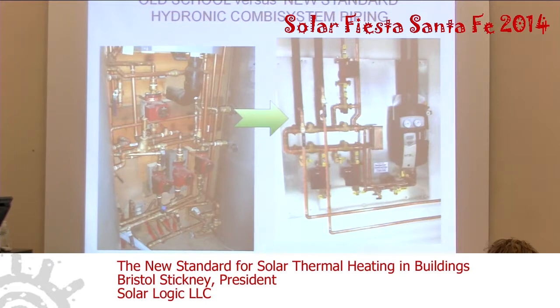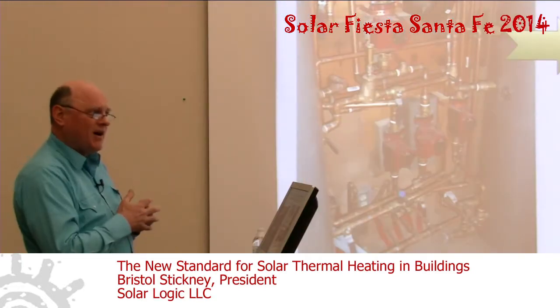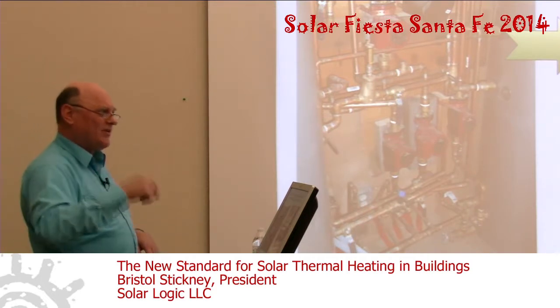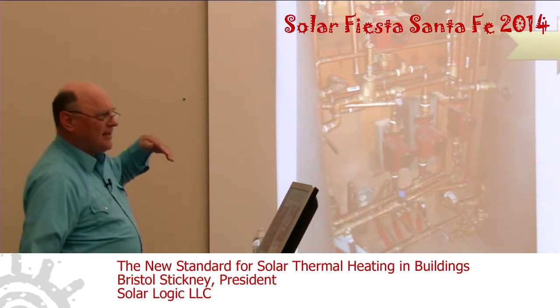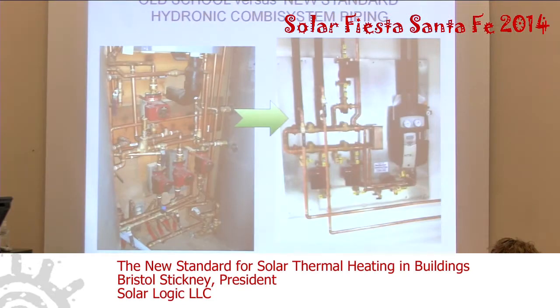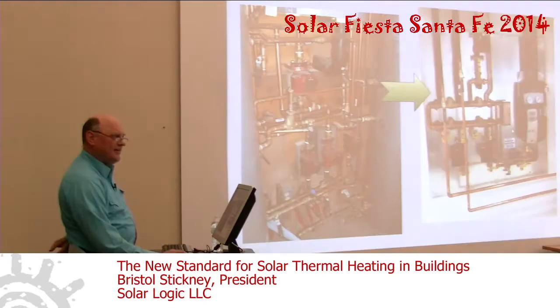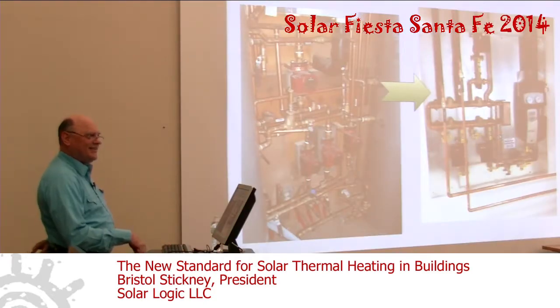It's a primary loop. It's a loop of plumbing with two T's taking heat away and pulling heat in, and a solar heat exchanger somewhere in the loop that delivers solar heat into the loop. So literally, these two plumbing photographs do the same thing. They both have 4 pumps. The 4 pumps do the same jobs. One pumps the boiler, one pumps the DHW, one pumps the floors, and one pumps the upstairs hot water baseboards. And then there's a pump for the solar. Okay, they all have the same number of pumps. They are all designed to do the same thing: heat the floor, heat the water tank, heat the hot water boiler, the hot water baseboards. But one is a nightmare and the other one is super clean and easy. Okay, the new standard makes it super clean and easy, plug and play.